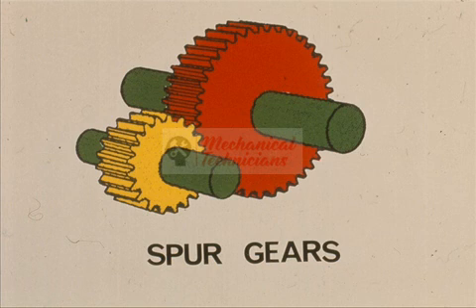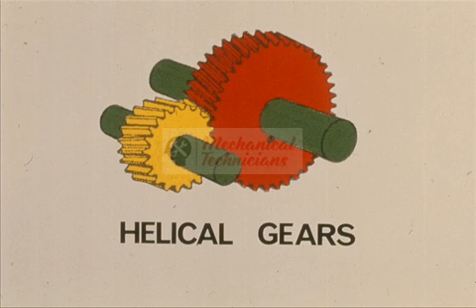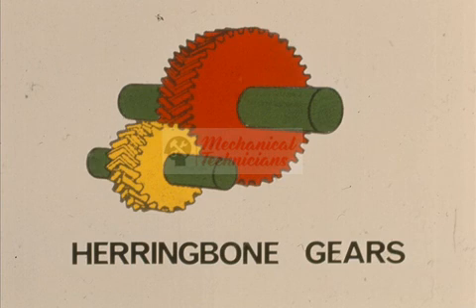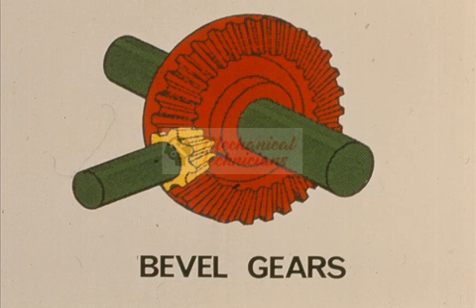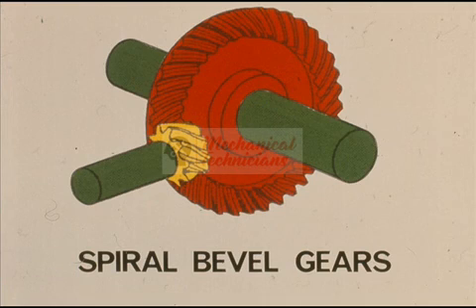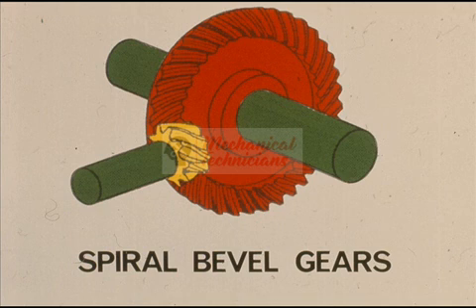Another important fact to consider in the selection of gearboxes is the types of gears they use. These straight tooth gears are known as spur gears, mounted on parallel shafts. These are helical gears, also mounted on parallel shafts — note the difference in the teeth. Also mounted on parallel shafts are herringbone gears, sometimes called double helical for obvious reasons. Other types of gearboxes utilize perpendicular or right angle gears, such as right angle bevel gears. Note the similarity between these gears and the spiral bevel type.